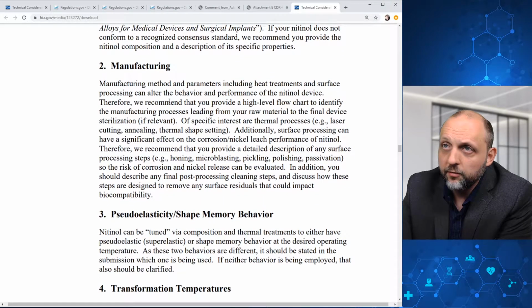And then in terms of manufacturing, FDA would like to know the manufacturing method and parameters, including heat treatments and surface processing that could alter the behavior and performance of the device. And they want to see a high-level flow chart to identify the manufacturing processes leading from your raw material to the final device sterilization if relevant. And of specific interest are thermal processes, additional surface processing as well.